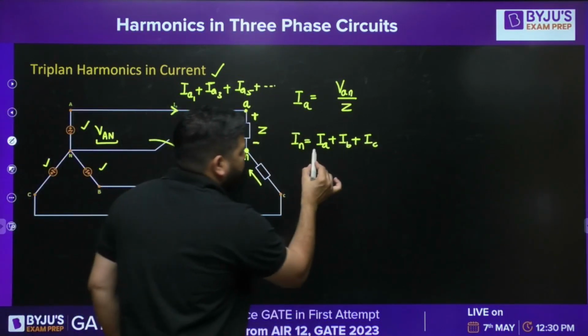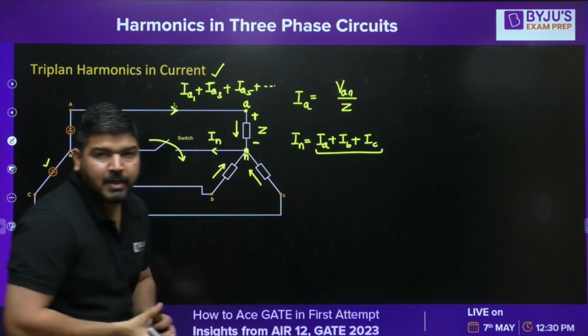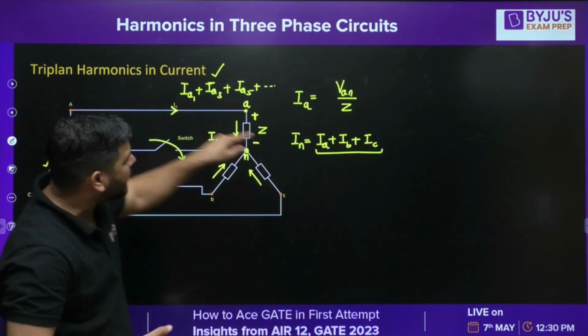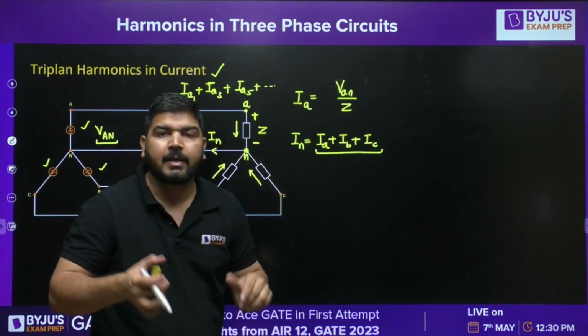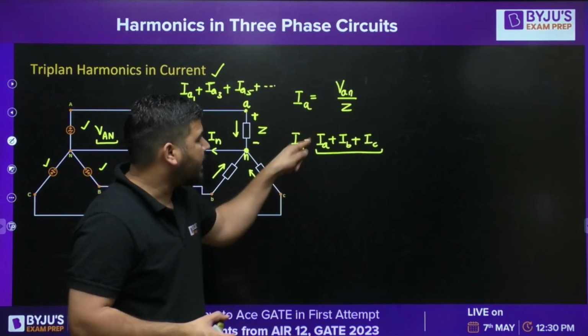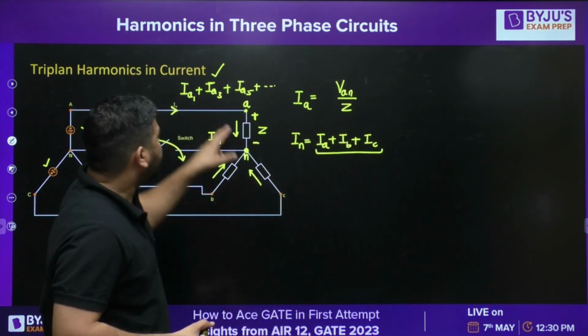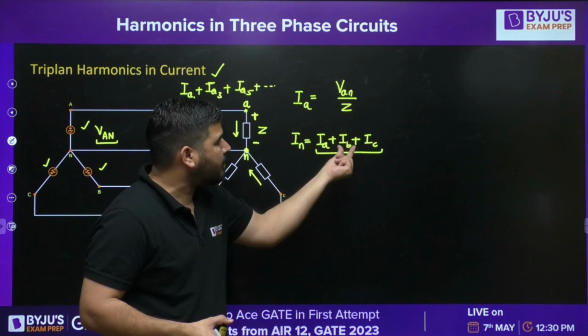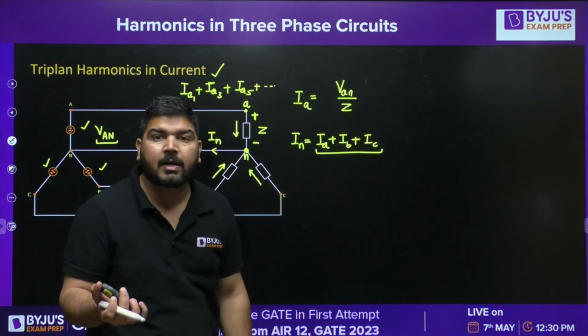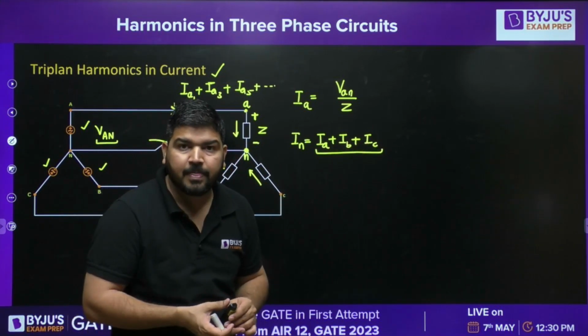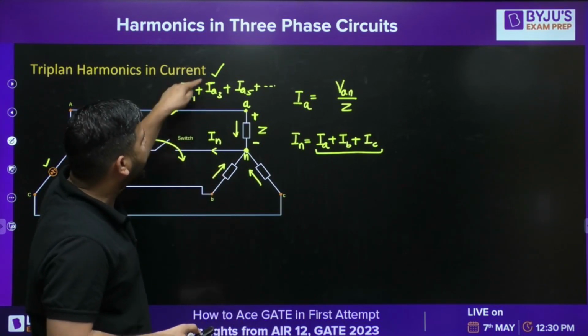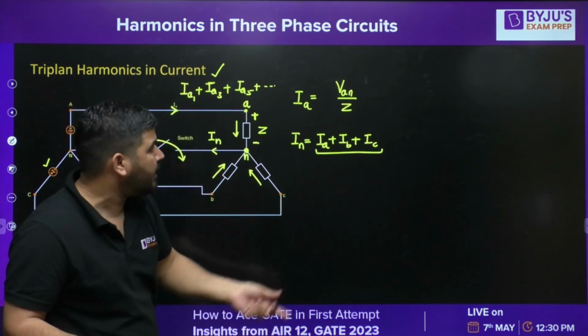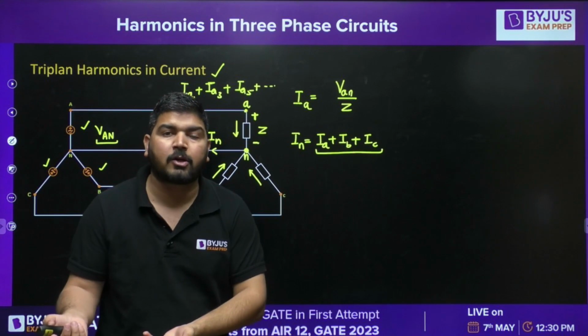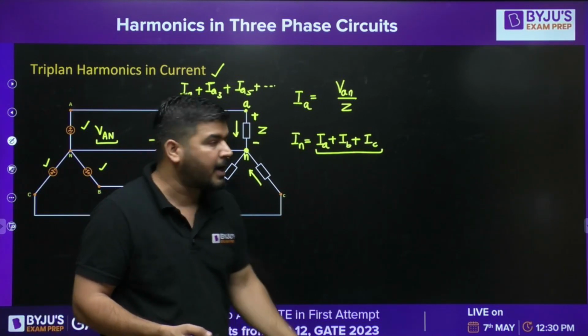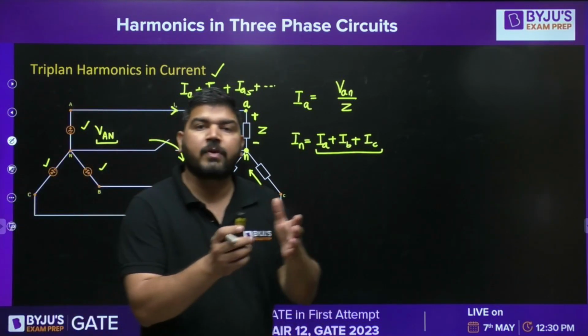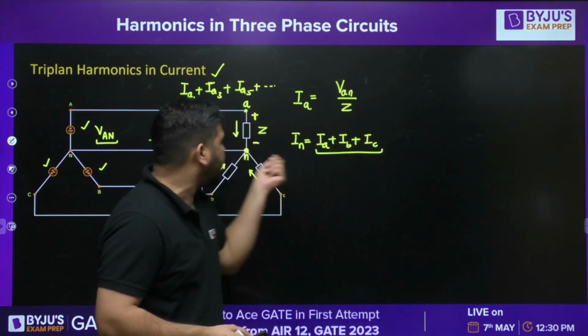If you add these currents, the fundamental current of each phase is 120 degrees apart, so they will cancel. But the third harmonic current in phase A, B and C will always be in the same phase - if phase A's third harmonic is sine 3 omega t, phase B and C will also be sine 3 omega t. Since the load is balanced, the magnitude will also be balanced.